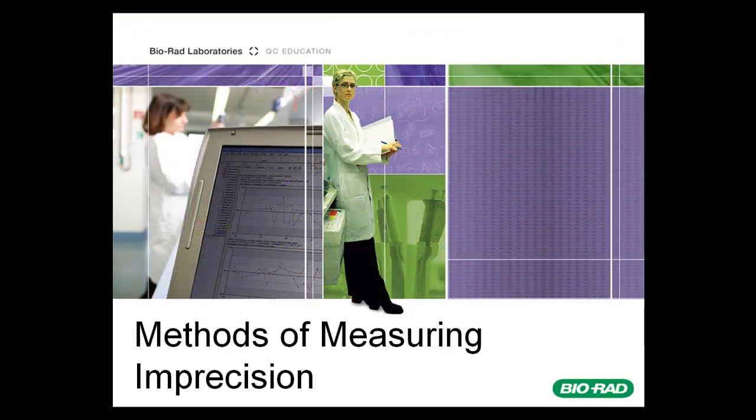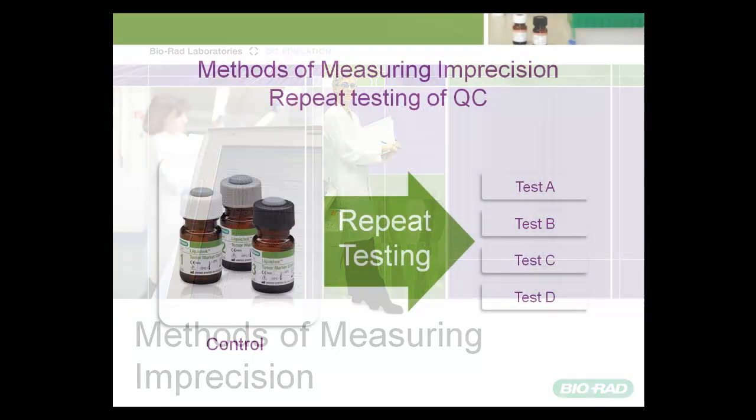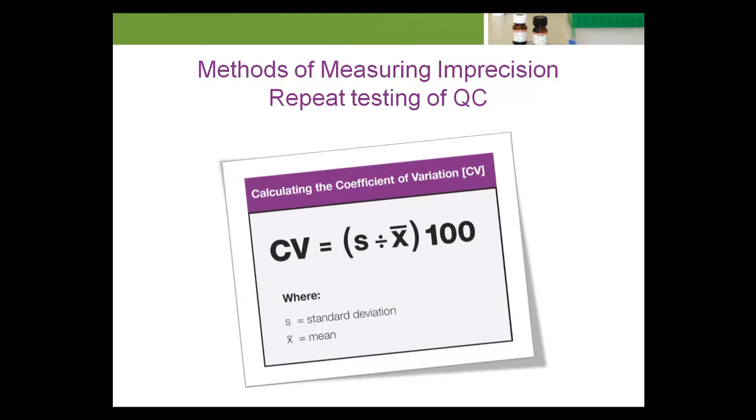Now that you have an understanding of what causes imprecision, we'll look at methods of measuring imprecision. One way of measuring imprecision is using data collected from repetitive testing of quality control materials. This method provides a good estimate of long-term random variation in actual everyday practice. The laboratory uses the data collected to calculate imprecision expressed as the coefficient of variation (CV).